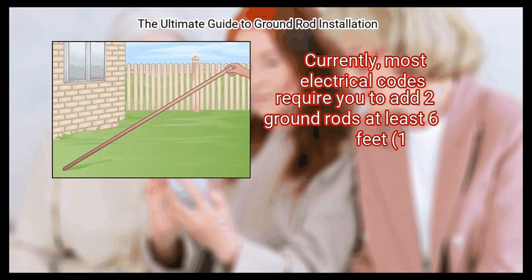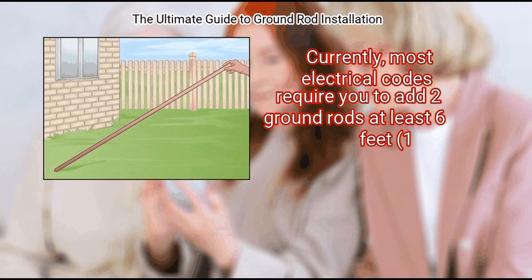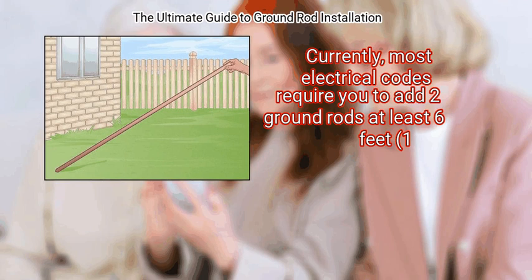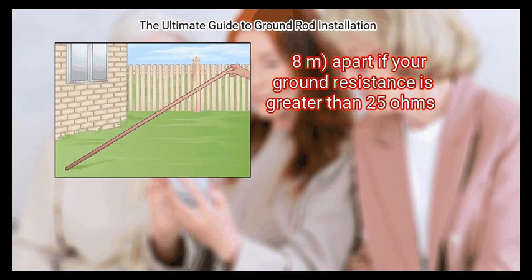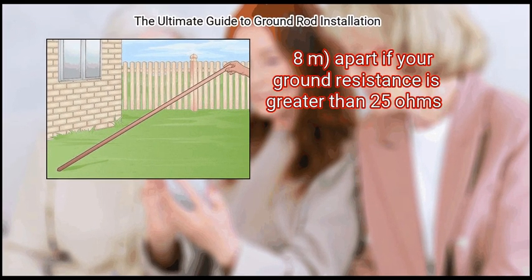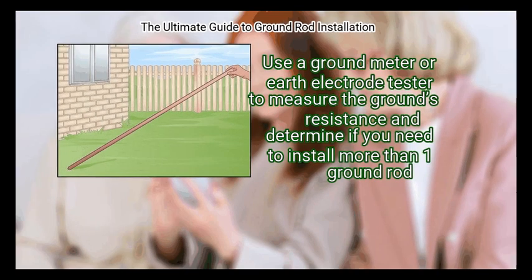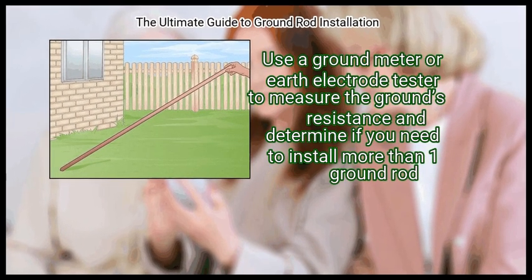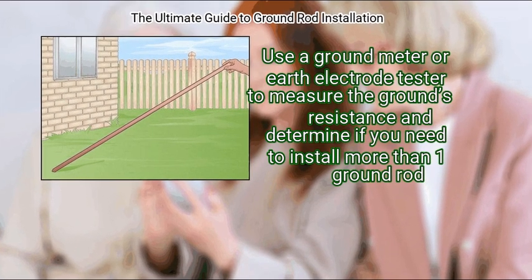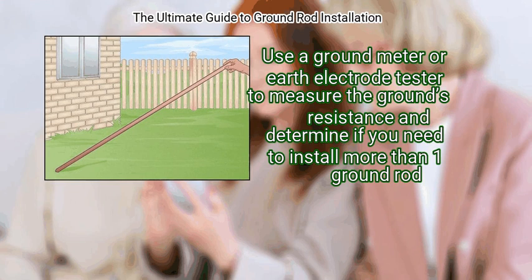Currently, most electrical codes require you to add 2 ground rods at least 6 feet, 1.8 meters apart if your ground resistance is greater than 25 ohms. Use a ground meter or earth electrode tester to measure the ground's resistance and determine if you need to install more than 1 ground rod.